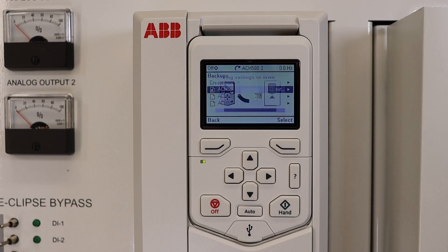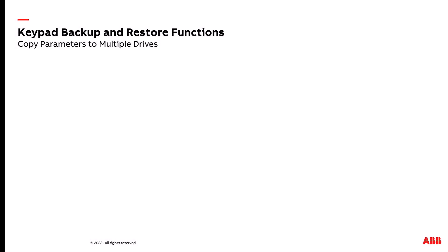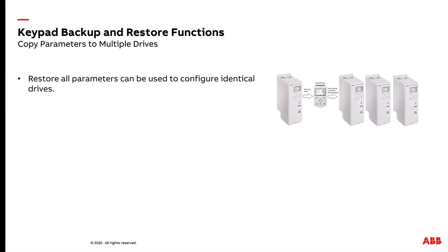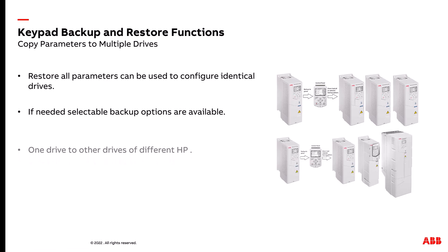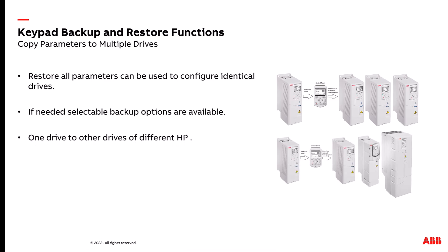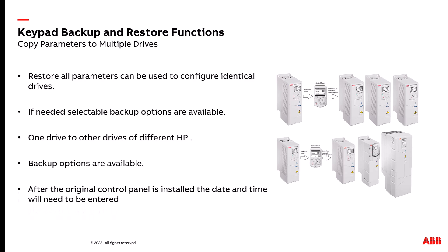This is all part of the ABB ACH 580 drive and the 580 series. Let's look at copying parameters to multiple drives. You can restore all the parameters from one drive to multiple identical drives. If the configurations are identical, you can back up from one drive that's set up and restore all the information to each individual drive. If needed, you can select backup options for individual parts of the parameter groups. One drive to another drive of different horsepower — backup options are available. After the original control panel is installed, the date and time will need to be entered on the original control panel.